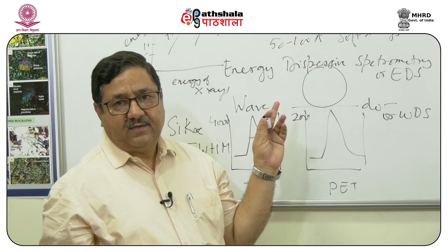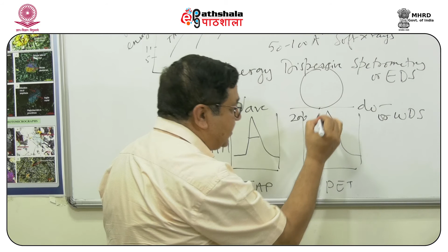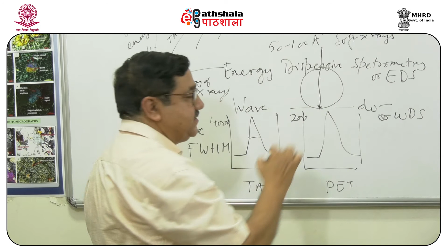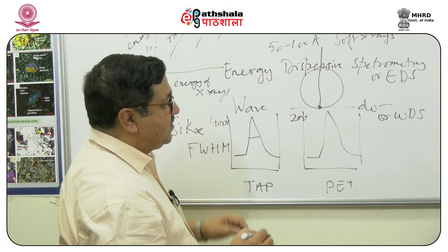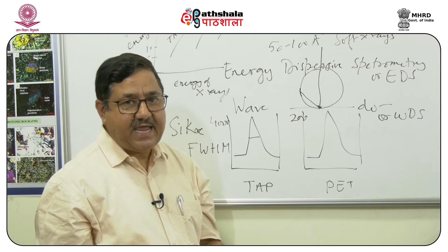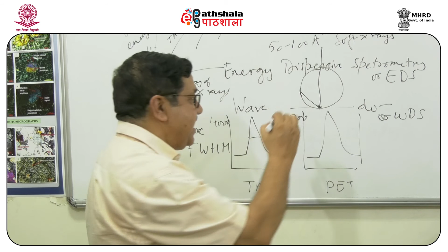Why do we do this? In WDS, or wavelength dispersive spectrometry, the sample is placed at a particular, unchanged point. The incident electron beam falls on it and generates characteristic X-rays. For a particular characteristic X-ray, we fix a diffracting crystal at the energy or wavelength position of that X-ray, and that is directed to a detector.